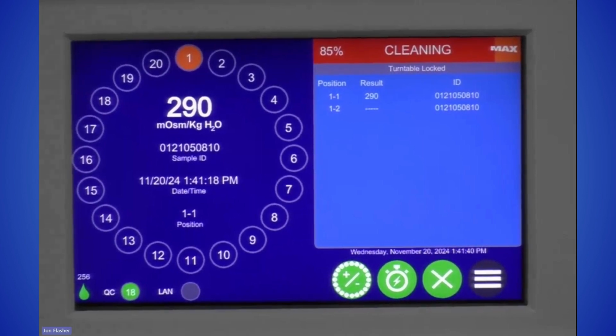Because we pre-programmed those duplicate tests to be run for each sample, it's just going to go right into cleaning, as it typically would following testing a sample. It's going to empty all of that out into the waste container, and then it's going to prime the fluidic pathway for the next test to be performed on that same sample. That's what it's going to do in between each test as well. So it's going to go ahead and just go right into the next one.